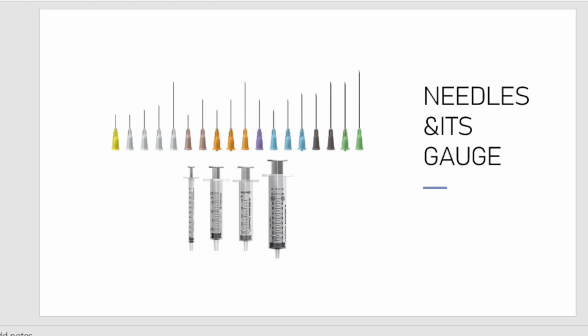The hypodermic needle gauge ranges from 18 to 27. For blood collection, the needle gauge is about 20 to 22. Butterfly needles are mainly used for small vein puncture, with a gauge size of about 21 to 25. Spinal needles, mainly for lumbar puncture, are about 22 to 27. For epidural, meaning for anesthesia, we use 16 to 18. For bone marrow aspiration, we use 11 to 15.